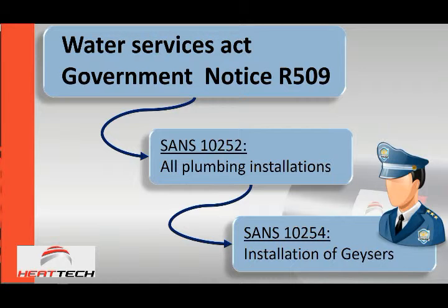And because SANS 10252 has a specific requirement that says when you install a geyser in any installation, the installation shall be in line with SANS 10254. Therefore, for all practical reasons, compliance with SANS 10254 is a legal requirement.